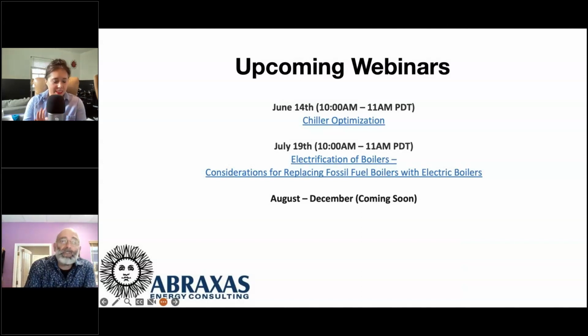Really, for that psychrometric chart we stayed on for a while, that's the inlet temperature of the rack. So when you're looking at the racks from the outside, like those thermal images I took, it's that temperature on the face, the temperature of the air going directly into the servers. We want to get it as close as we can to 80 degrees ideally, to save as much energy as possible.